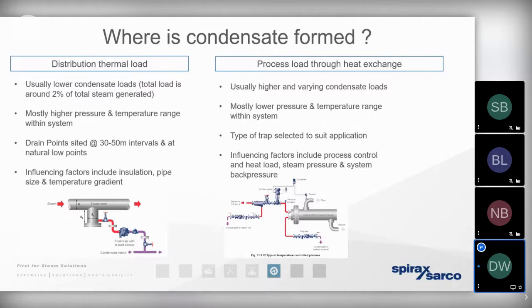So that 2% rule of thumb applies to what we refer to as the running load, but we always double that 2% to 4% to allow for that higher warming up load. Now, if we hadn't allowed for that warming up load, then the steam traps would be significantly undersized. And that's when we're at risk of that condensate backing up and slowly starting to flood the distribution network. And when that happens, of course, we're going to see erosion, corrosion, water hammer, and we're likely to get steam finding its way to the process with significantly less energy contained within it because it's now wet steam.